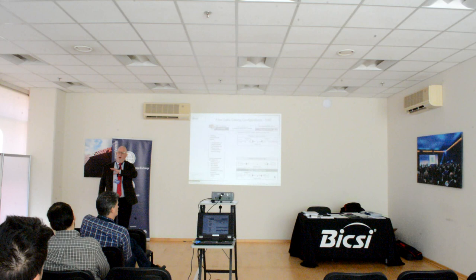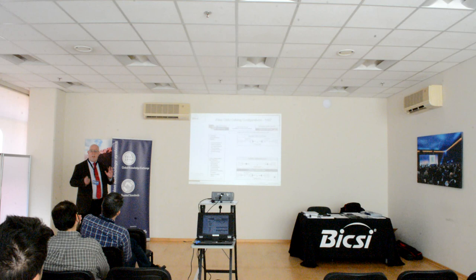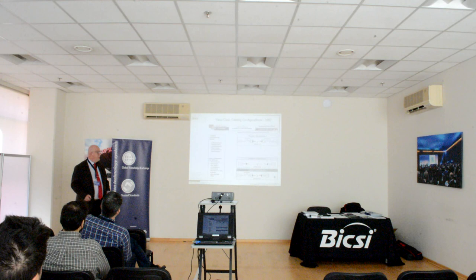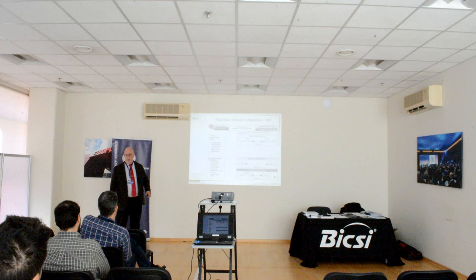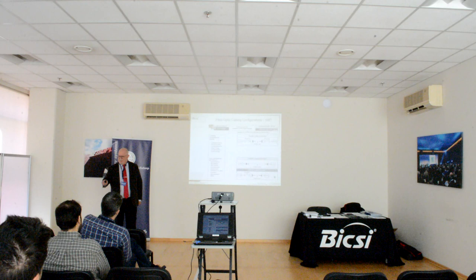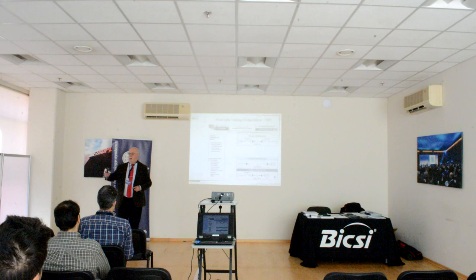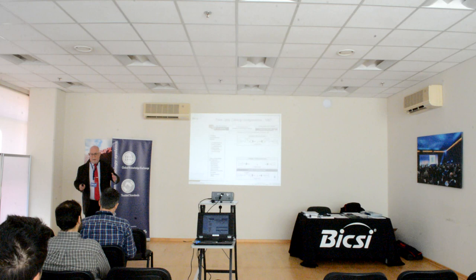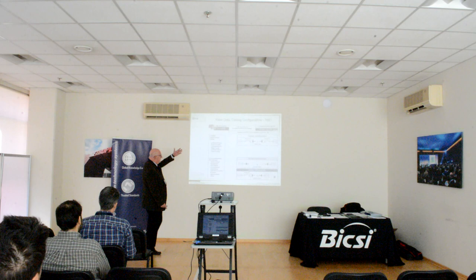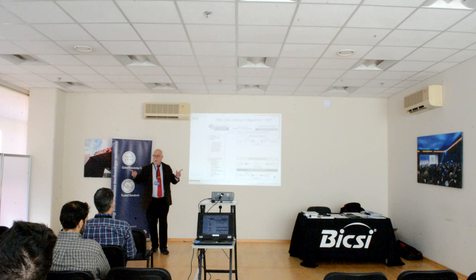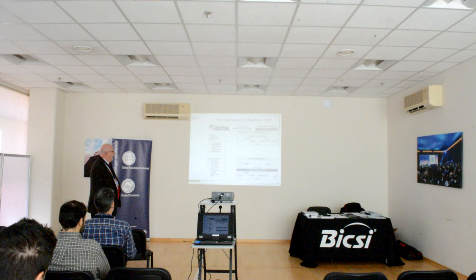And at that time, there were no written down test methods. What there were about 15 people in a room with me who said, that's how you should do it, that's how you should do it, and that's how you should do it. And how you do it depends upon what you're testing. Are you testing a plug to a plug, an adapter to an adapter, or an adapter to a plug? Three configurations. Adapter to adapter is configuration A, panel to panel. Configuration B is plug to plug, and configuration C was plug to panel. Those were the only three possibilities. They still are really the only three possibilities.